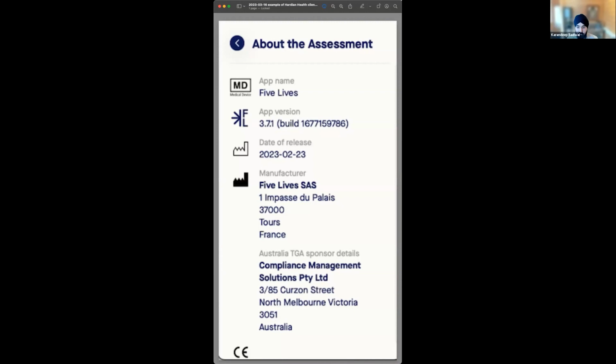A question from Berner, sorry if I said your name wrong. Hi, is the ref number from the catalog number? I mean the model number. You can make up whatever it is that's relevant. We normally put the ref number as the version number of the software. Like here, 3.7.1. See, there's a little mistake in this one, that they've put their logo instead of the word ref. And actually there's a little mistake in the COVID app one as well, that they formatted the date wrong, but they're just minor stuff and you can tell what they mean.